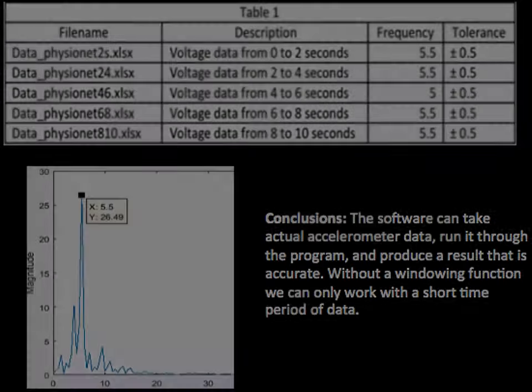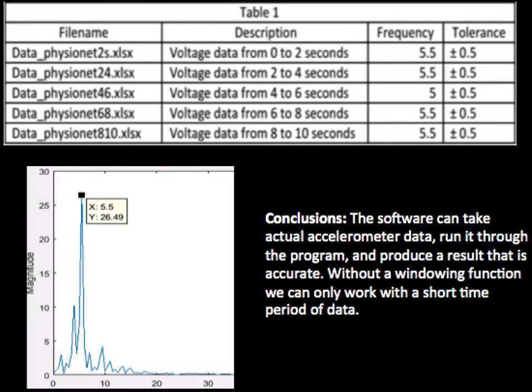The Eureka software has been validated using real tremor data pulled from PhysioNet. The Eureka team calculated the clinical tremor by hand and then ran Eureka to confirm the results. Eureka was able to match the hand calculations confirming the software is valid.